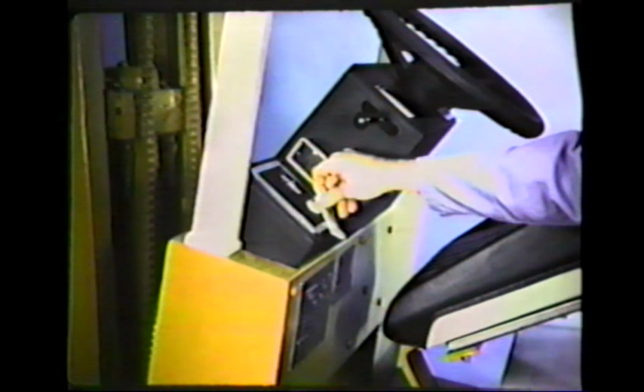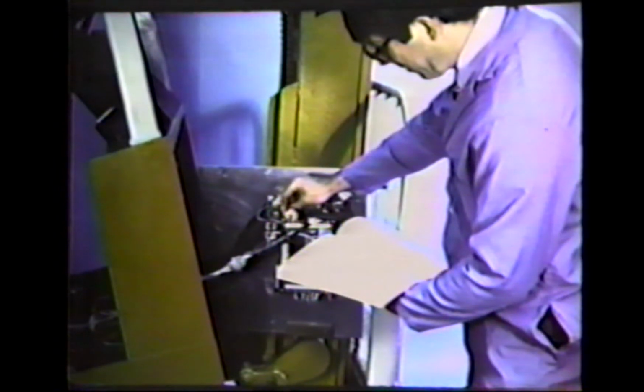Troubleshooting system malfunctions on the EV-1 control is simplified due to the way the switches and various other components are wired into the L and R terminal strips. Also, the PMT operation of the control helps to isolate problems quicker. In the following slides, we will look at some of the more common symptoms and then some of the voltage or resistance checks that you can make to locate the cause of the symptom. For more detailed troubleshooting procedures, refer to the Electrical SCR Manual, STL 1207, that is available through the Training and Development Center.